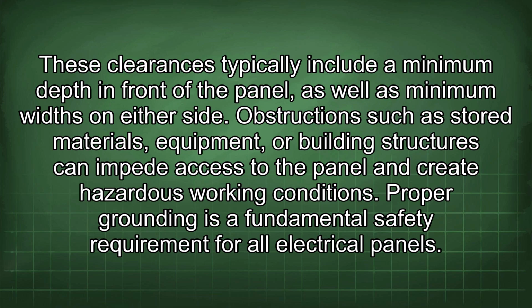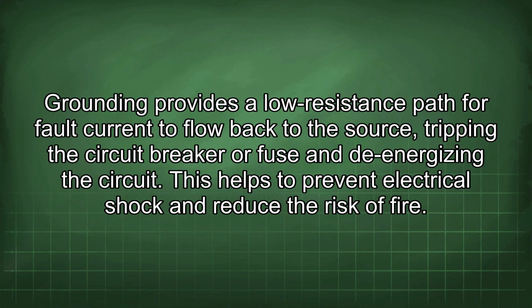Proper grounding is a fundamental safety requirement for all electrical panels. Grounding provides a low-resistance path for fault current to flow back to the source, tripping the circuit breaker or fuse and de-energizing the circuit.